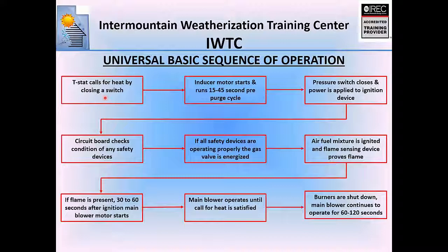In this case, for the rest of this presentation, we'll just be talking about heat since we're getting into the heating season. Anyway, the switch in the thermostat closes, which tells the furnace to start running. The inducer motor starts and runs a 15 to 45 second pre-purge cycle. A pressure switch of some sort is going to close, and power is then applied to an ignition device, typically a hot surface igniter, but there are some spark ignition systems out there.